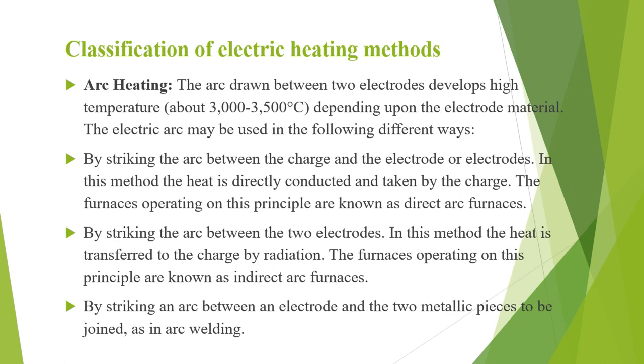Arc heating: the arc drawn between two electrodes develops a high temperature of the order of 3000 to 3500 degrees Celsius depending upon the electrode material. The electric arc may be used by striking the arc between the charge and the electrode or electrodes — in this method the heat is directly conducted to the charge. The furnace operating on this principle is known as a direct arc furnace.